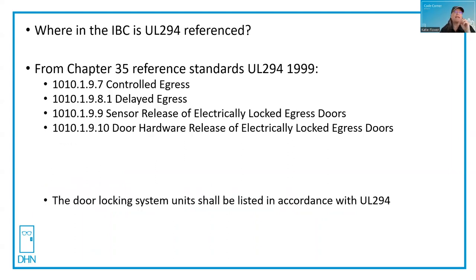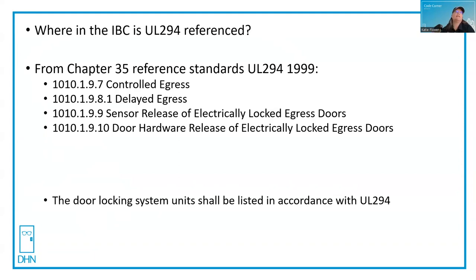In Chapter 35, they have reference standards — that's the name of the chapter. UL 294 1999 edition is referenced by section 1010.1.9.7 for controlled egress, 1010.1.9.8 for delayed egress, and 1010.1.9.9 for sensor release of electrically locked egress doors.